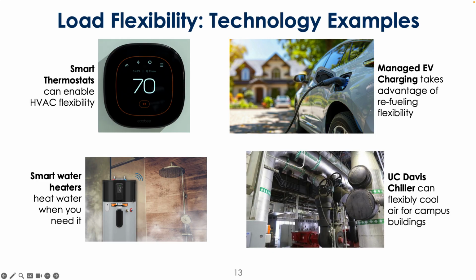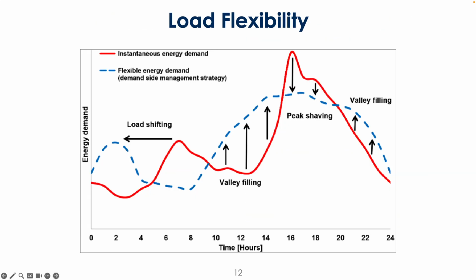But then the algorithm was created by the grad student in chemical engineering, but Devin did help with some of the coding and I believe constraints, as well as building screens that the operators use to know what they ought to do at a given time. So when we think about the load flexibility here, the objective function of the chiller was to be responsive to prices, right? Do you know how much money you saved with that algorithm?